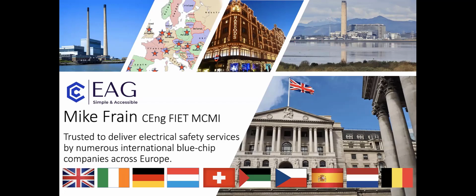What are you doing there in the first place? And there'd be no need for all this, I don't think, if people actually worked on equipment in a proper manner and maintained it in a proper manner. And notwithstanding that, I deal with sites where you've got equipment which is, believe it or not, 50 or 60 years old, and that was manufactured to a far different standard back then. Some would argue, by the way, that it was copper-bottomed standard, cast iron and things like that. But I'm afraid sometimes the incident energy, calculating the amount of hazard within the switchgear itself, points towards what could happen.